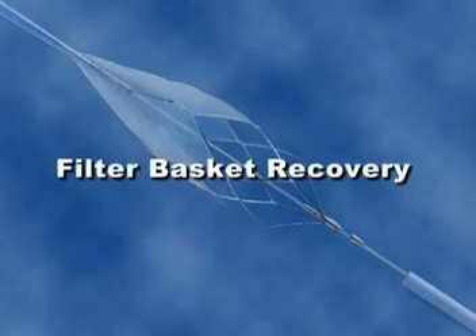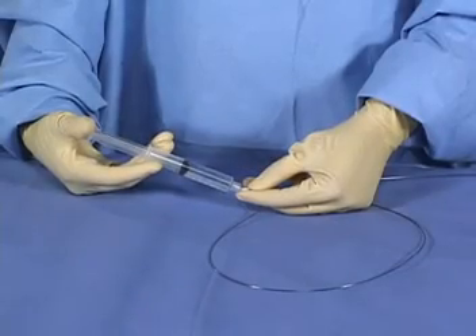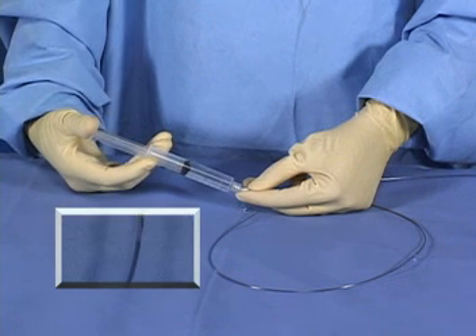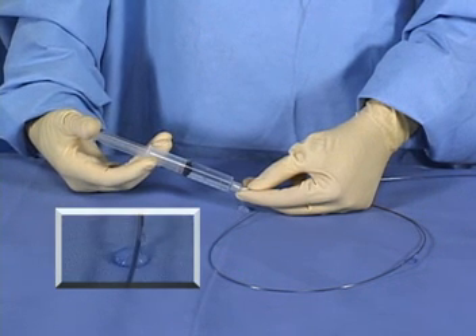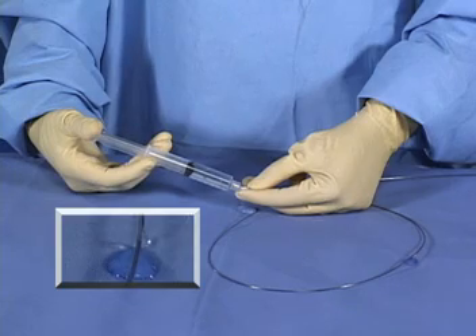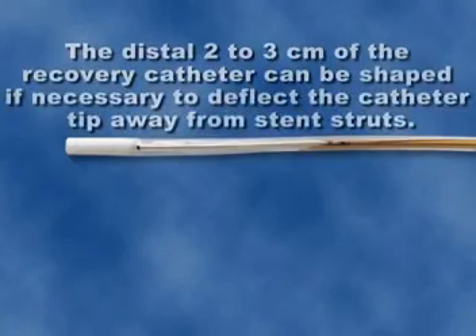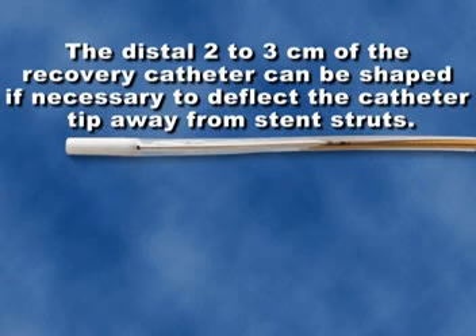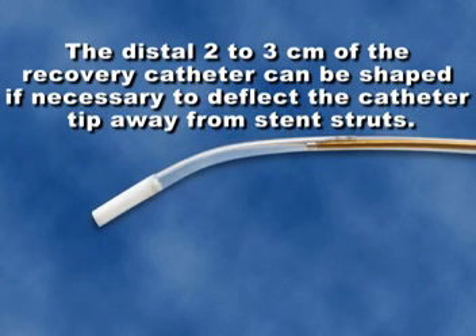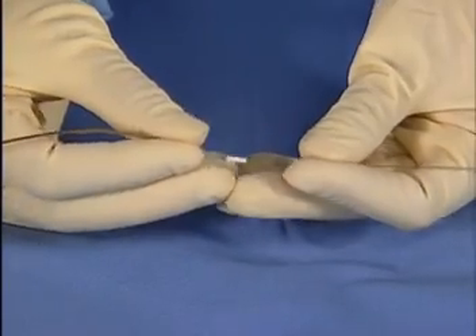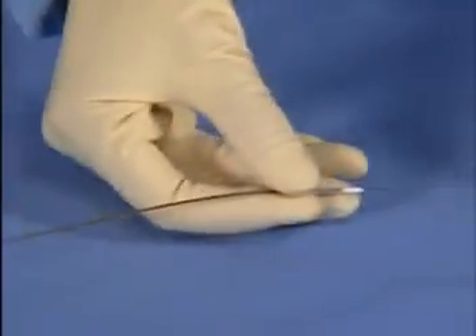Filter basket recovery. Remove the recovery catheter from the dispenser hoop and flush the distal end. Observe fluid exiting from the RX exit notch. The distal 2 to 3 centimeters of the recovery catheter can be shaped if necessary to deflect the catheter tip away from stent struts.